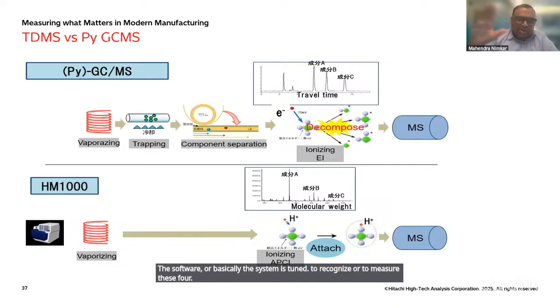It doesn't require much sample preparation. You just cut the sample, let's say if you have a plastic sample, weigh it, and keep it in the HM1000 auto sampler. Automatically it gets heated up, vaporized, and goes to the MS. The system is tuned to recognize and measure these four phthalates, so automatically you get the results on the screen. That's quite easy, I would say.